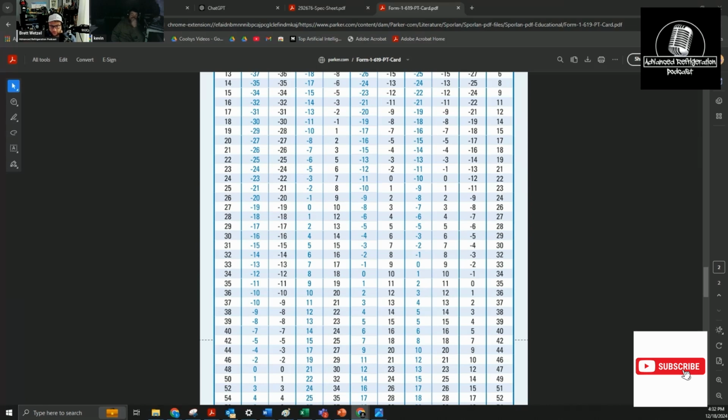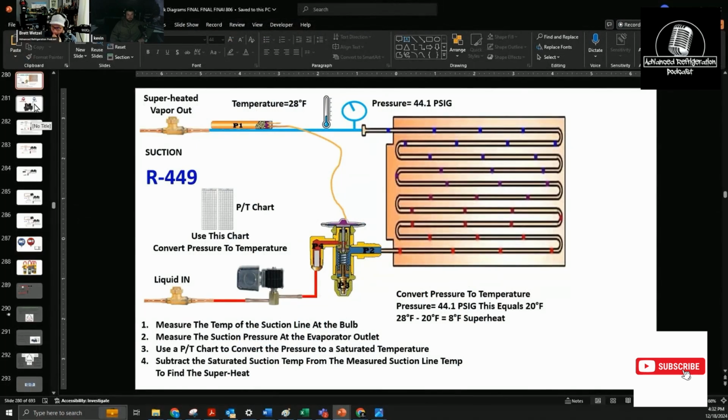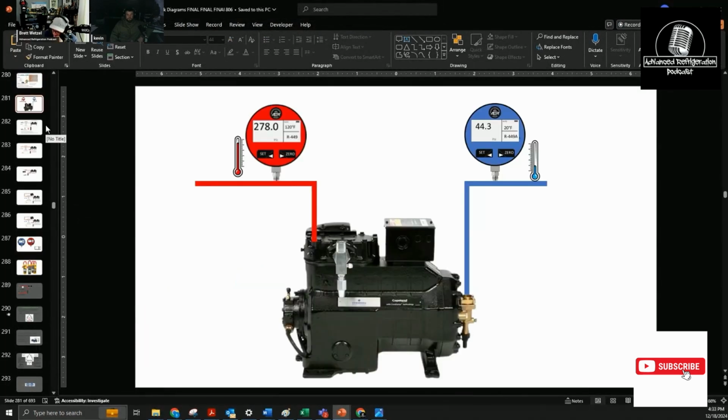Yeah, no, well, the other thing is all these manufacturers underrate those heat exchangers. They are efficient. Some of them have like a 2 to 3 degree approach temp on them. It's way more efficient than what they say it is, which is a good thing. There's nothing wrong with running it more efficiently. You're running a higher saturated temp. So this, just subcoolers, that's a big thing, setting it up.